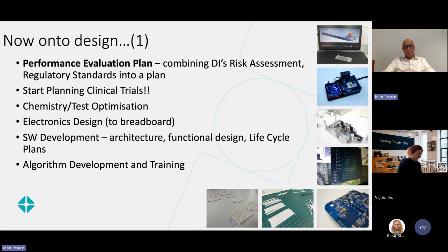Now, in some cases, for PMAs and for de novo products in the US, you need to agree the clinical trial protocols in advance with the FDA. So it makes sense to engage with FDA as early as possible on those types of projects. I'll come to that in a minute as well. And then at this stage, early in the project, you're doing the test chemistry optimization, electronics design, if there is an electronic instrument or an electronics element to this diagnostic test, software development, and also the algorithm development. So understanding the interpretive software, how the biomarkers or the patient information or whatever is going to be processed to generate the diagnostic statement. So early in the development program, you should be working on these areas.